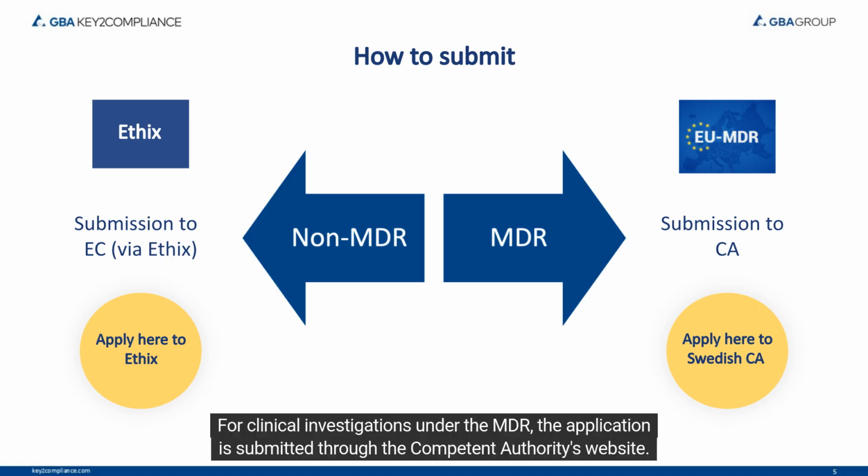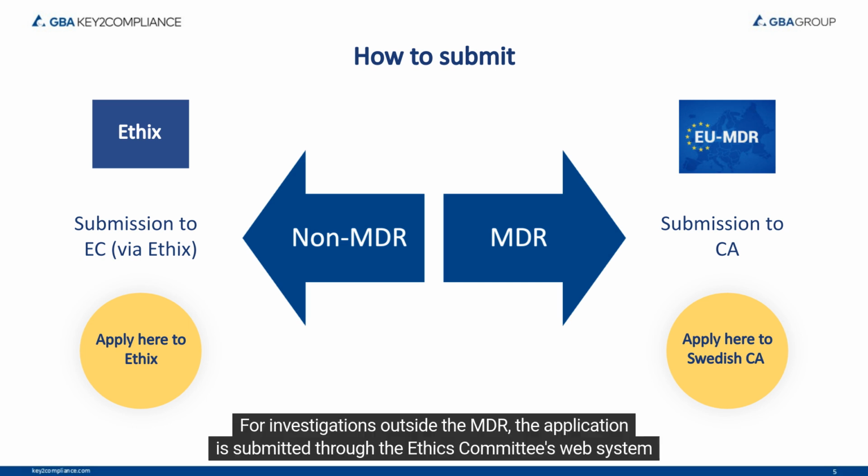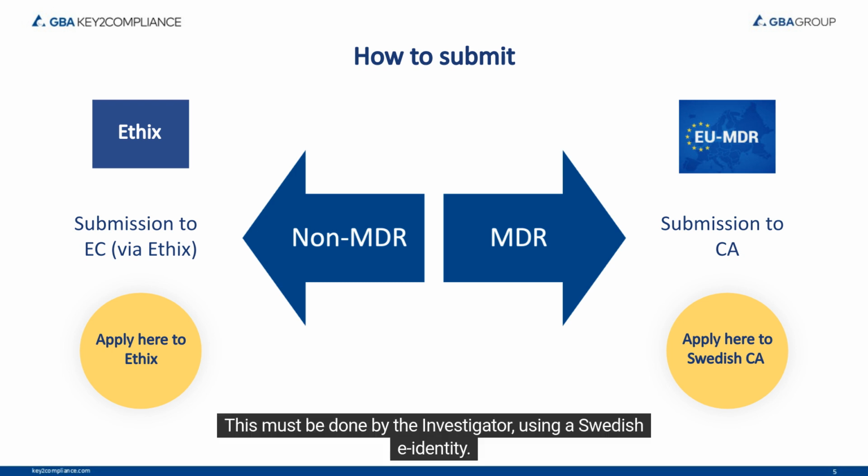For clinical investigations under the MDR, the application is submitted through the competent authority's website. For investigations outside the MDR, the application is submitted through the Ethics Committee's web system called Ethix. This must be done by the investigator using a Swedish e-identity.